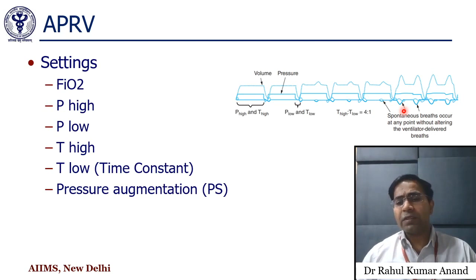To wean a patient, the methodology is drop and stretch. What we do is we decrease the inspiratory pressure and we stretch the inspiratory time from 5 or 6 seconds to 10 or 12 seconds. The inspiratory pressure, the P high, is decreased from maybe 25 or 28 to 20, then less than 15. And once the P high is 15 or 16 and the T high is around 10 seconds, we can switch the patient from APRV to pressure support.